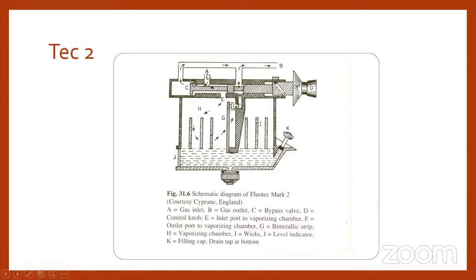And A is the inlet valve, which admits the fresh gas. When the control knob is closed and in off position, only fresh gas will flow through the channel and it will be delivered to the patient. When we open this knob, some amount of fresh gas will enter the vaporizing chamber. It goes through all the wicks that are present in this and it mixes with the vapor, and this vapor will be transmitted to the main pipeline through this channel and it mixes with the fresh gas and forms a mixture of anesthetic and will be delivered.